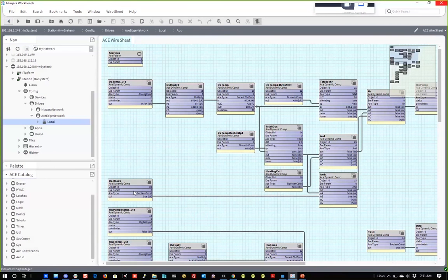So it's the standard T-stat and loop point stuff, and the same integration constants and mathematics that you use to generate throttling range and integration? Yeah, you still have your HVAC logic in here. It's the same loop, because I took screenshots of my existing application and then used that to rebuild this exactly the same. And the calculations, the way that the integral and derivative and throttling range work, are exactly the same.